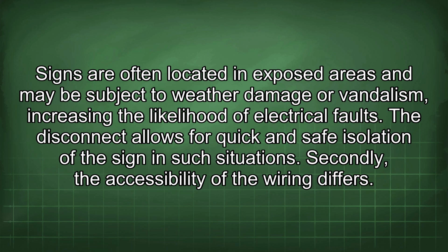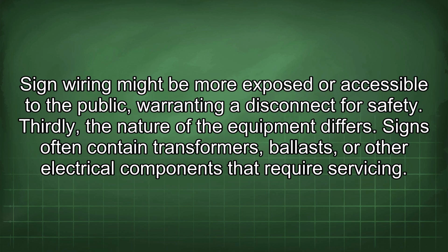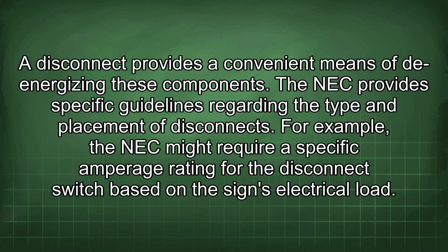Secondly, the accessibility of the wiring differs. Sign wiring might be more exposed or accessible to the public, warranting a disconnect for safety. Thirdly, the nature of the equipment differs. Signs often contain transformers, ballasts, or other electrical components that require servicing. A disconnect provides a convenient means of de-energizing these components. The NEC provides specific guidelines regarding the type and placement of disconnect. For example, the NEC might require a specific amperage rating for the disconnect switch based on the sign's electrical load.